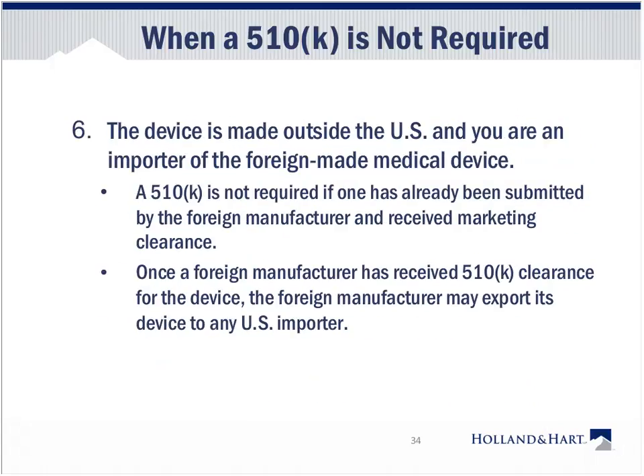You're also not required to file a 510K if the device is made outside the U.S. and you are an importer of a foreign-made medical device. So a 510K is not required if one has already been submitted by the foreign manufacturer. And by the way, the foreign manufacturer is required to submit a 510K and receive marketing clearance. Once the foreign manufacturer has received 510K clearance for the device, the foreign manufacturer may export its device through a U.S. importer. The U.S. importer does not need any additional clearance from the FDA.